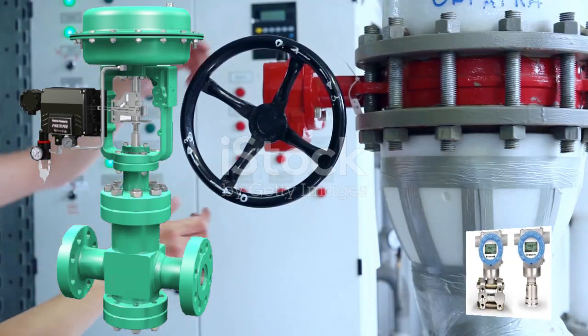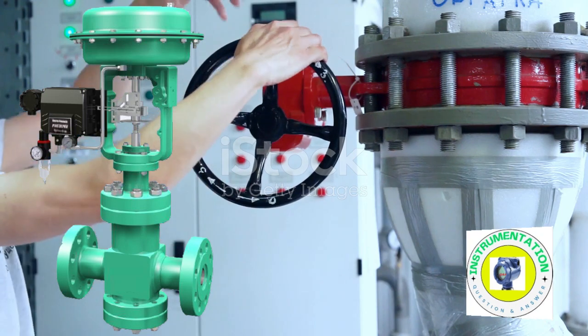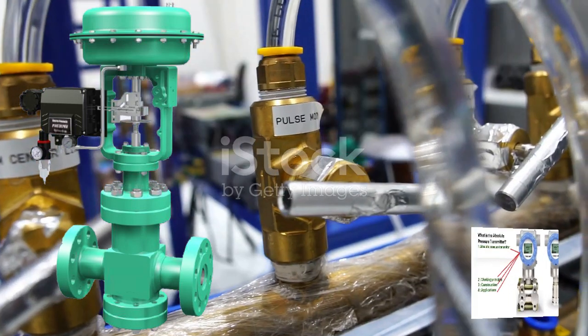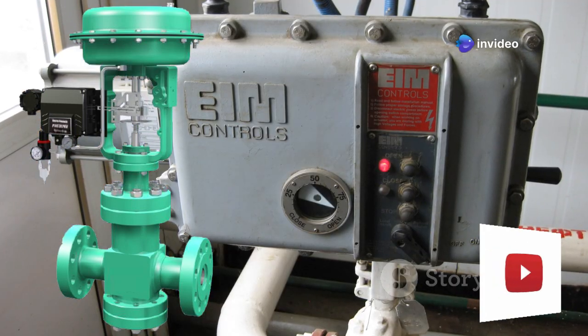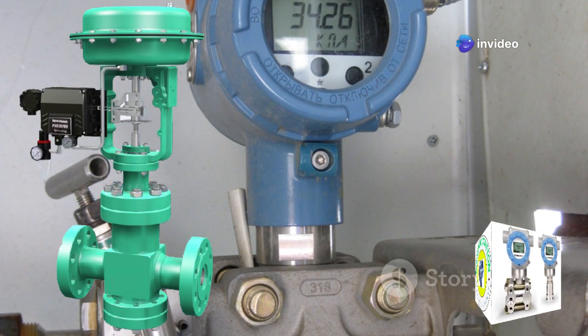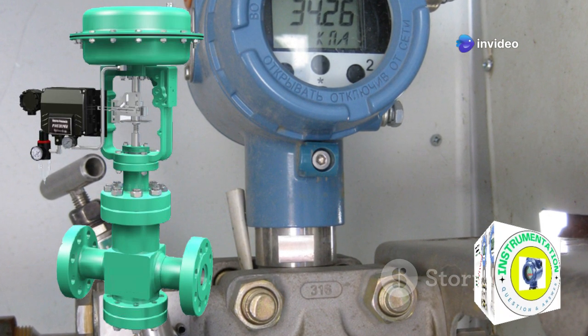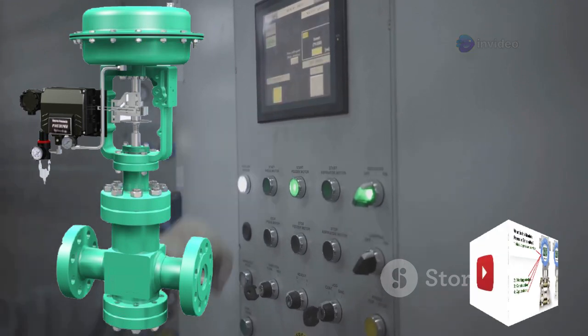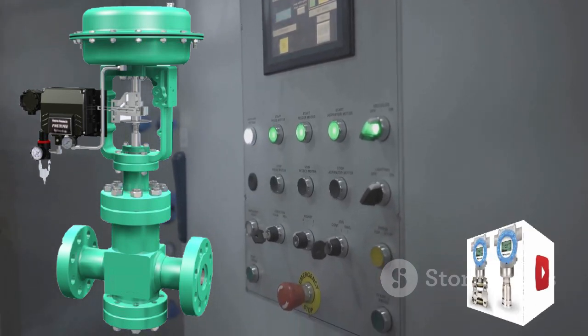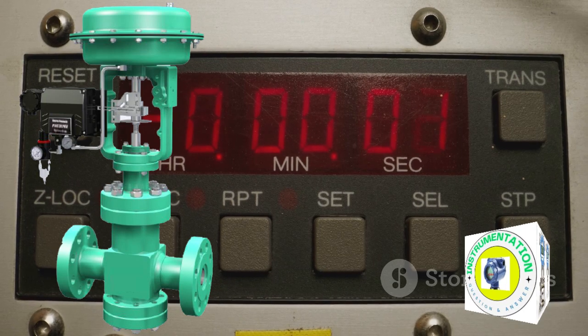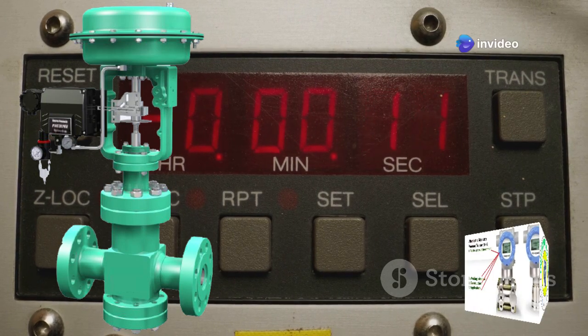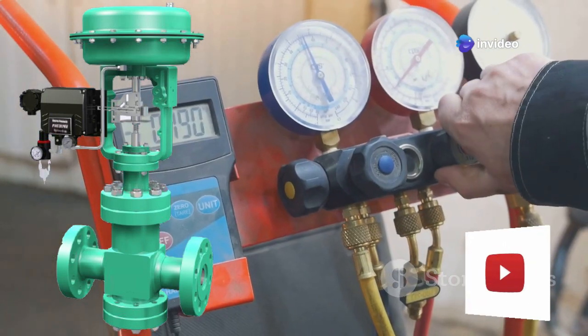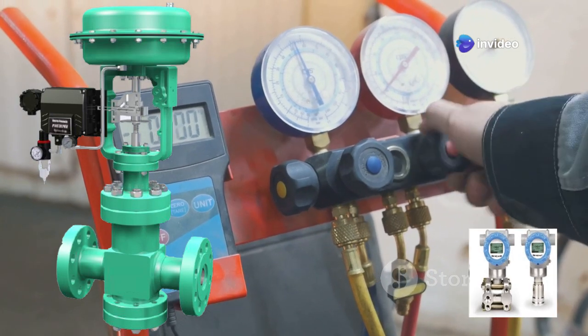The positioner will automatically move the valve to fully closed, 0%, then fully open, 100%. During this, it's mapping the valve's travel limits and calibrating its feedback sensor. It'll even tweak its own PID or gain settings so you get the best response. This process typically takes between 1 to 3 minutes. Just let it do its thing, but sometimes auto-calibration doesn't nail it, or you need extra precision.